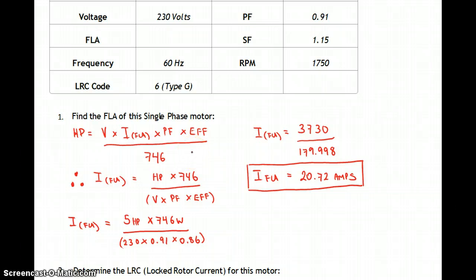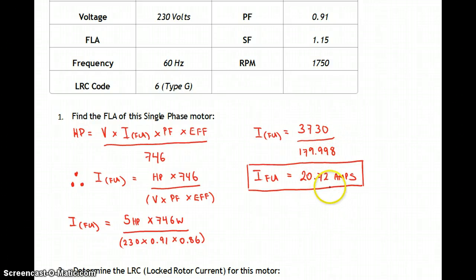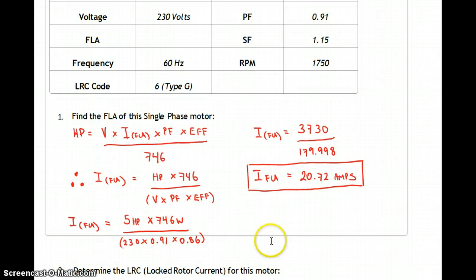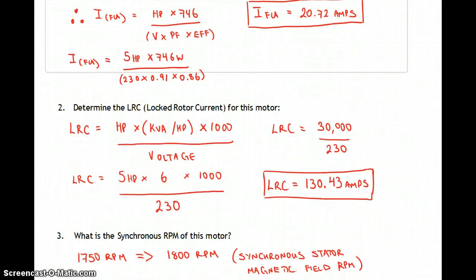So we have 5 horsepower — each horsepower is 746 watts — divided by our voltage 230 times 0.91 times 0.86. That gives us 3,730 over 179.998. The full load current for this 5 horsepower motor is 20.72 amps when running at 230 volts. That's the full load current when it has the maximum load on it.